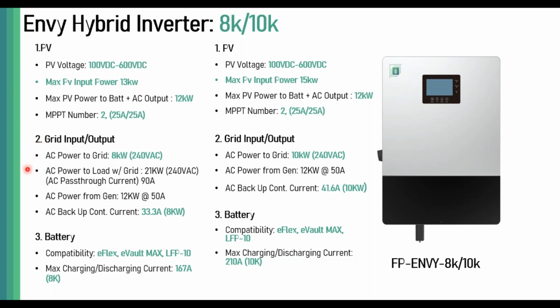Okay, it has a generator port as well, and it can do AC pass through up to 90 amps. Okay, 90 amps, as well as the AC coupling capability, the same as the 12K. And with the battery, it has a max charging and discharge current capability of 167 amps for the 8K, and then 210 amps for the 10K.